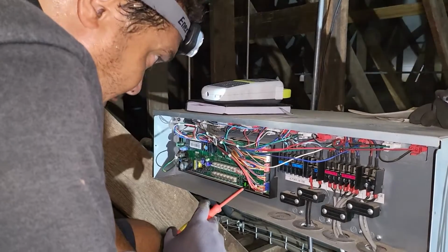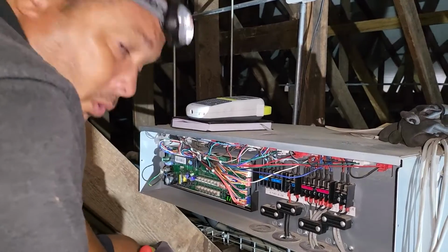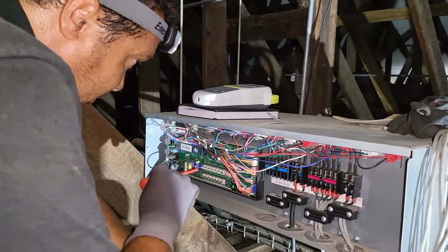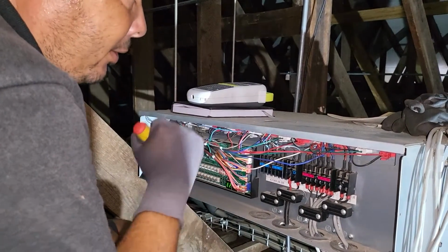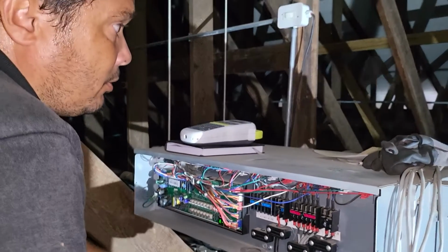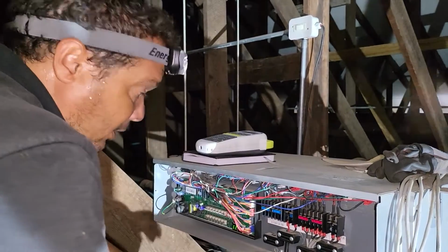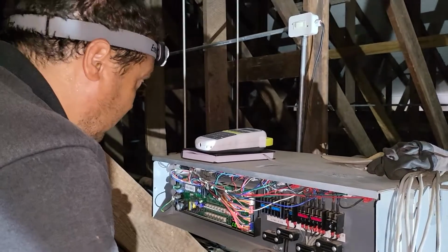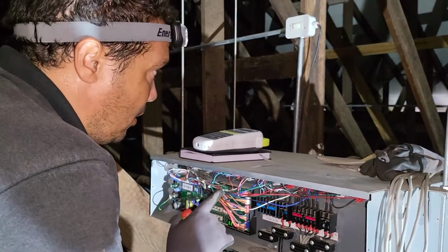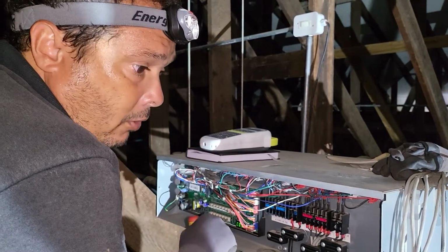Okay, so there's a couple of things here. We are at MCU 2 now, and we've taken down all the addressing, and there's something interesting happening on this MCU. Firstly, you have two RefNet branches on circuits, one on A to B, and then one on C to D, and then E to F on single systems or single pipes, which means we've effectively got 4 systems on this 6 system MCU.